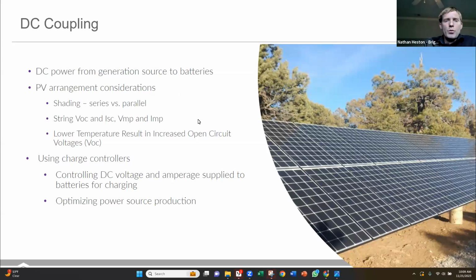Charge controllers are equipment that use DC inputs to be able to supply batteries for charging. And some systems have charge controllers built into them, in the case of hybrid inverters. But we're going to talk a little bit about historical equipment as well. And we don't want to leave that off-grid community behind either, because it's often a lot cheaper to go with those older components or with those smaller components for off-grid systems. We'll talk a little bit about optimizing power source production as well.